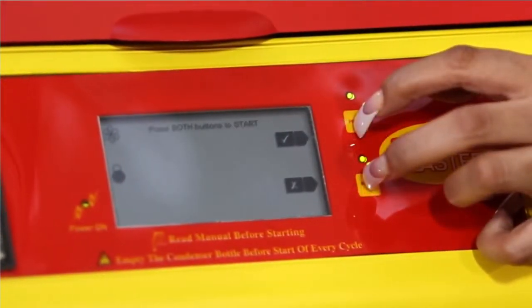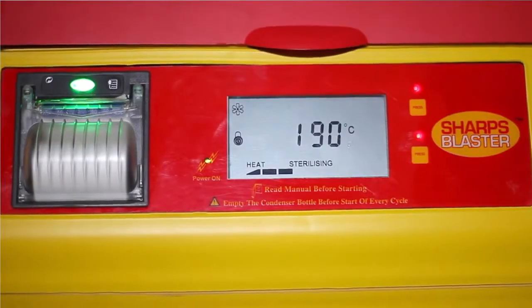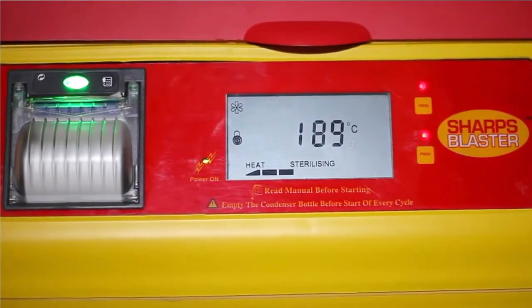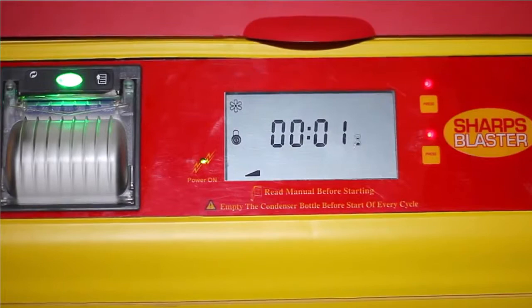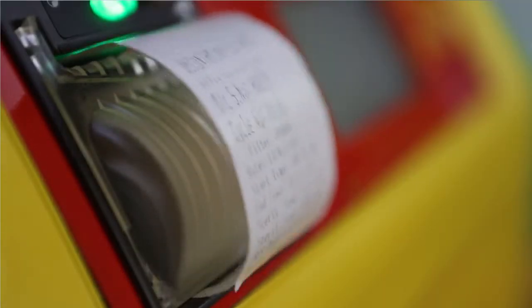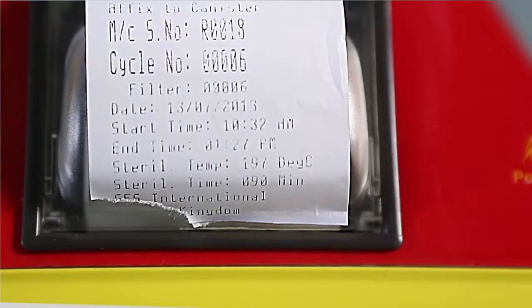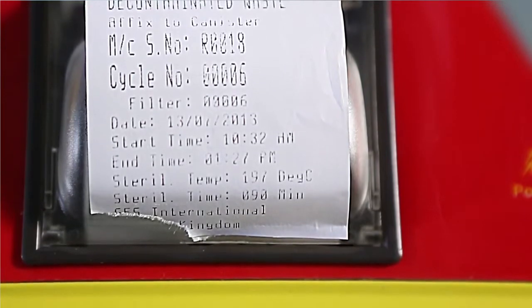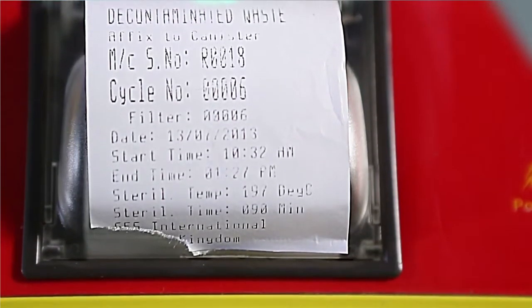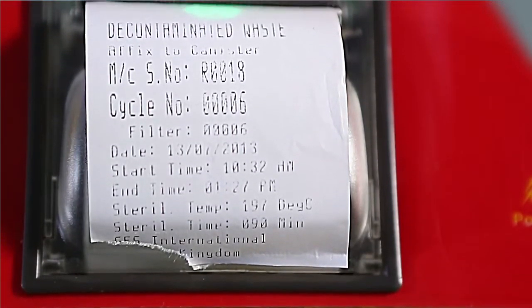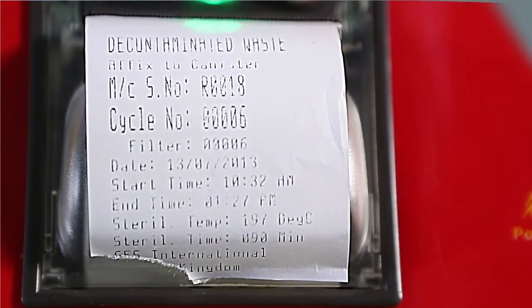First press the start button. Now press both buttons together to start, and hold for about 4 seconds. The sterilization cycle lasts for about 2.5 hours. Once the treatment cycle is over, it automatically generates 2 tickets confirming the disposal details such as temperature, duration of sterilization, date, time, and cycle number.